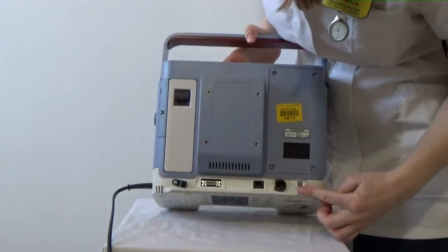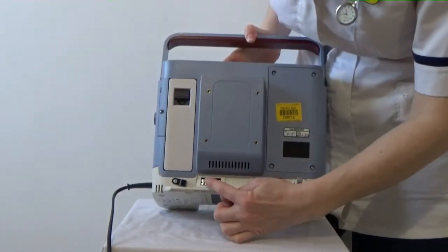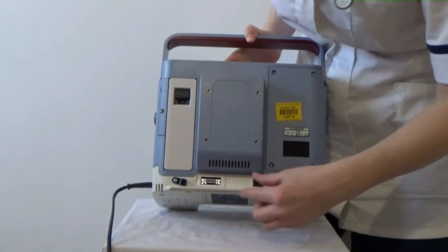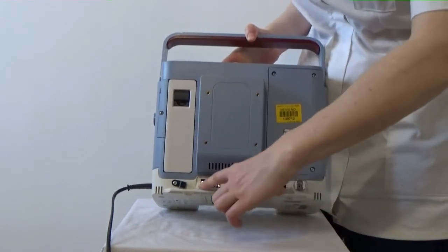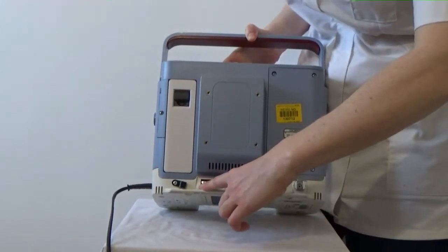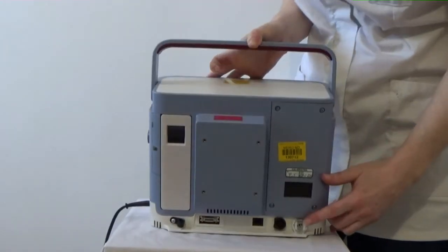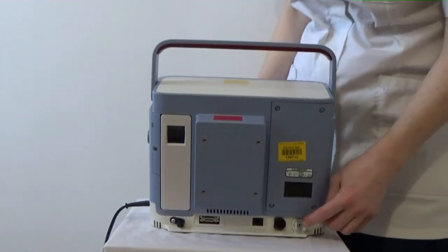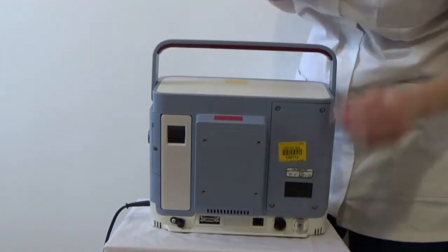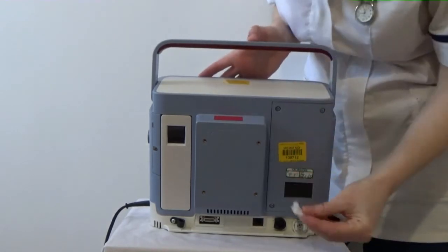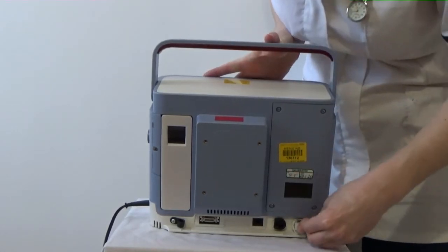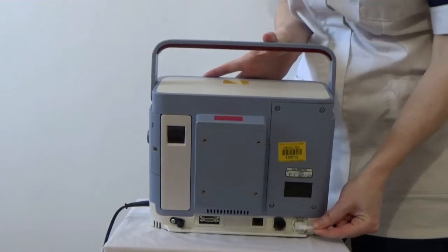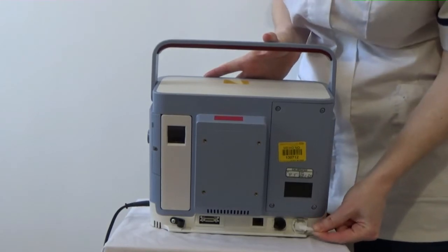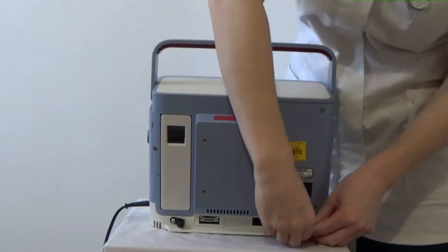At the bottom here we have ports where we can connect the ventilator to the computer and to an oxygen probe. However, we don't tend to use these two. This here is where oxygen can be entrained if it is required. To access this, a nipple is needed and this clicks into place. Oxygen tubing is then placed onto the nipple. However, this must be removed if oxygen is not being used.